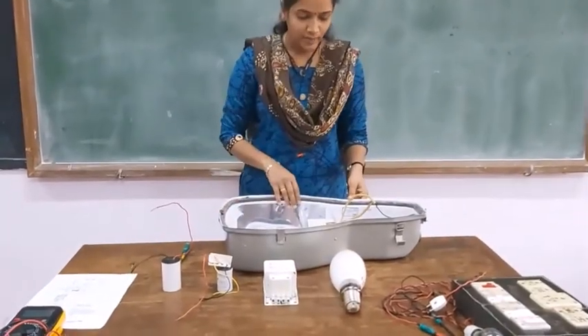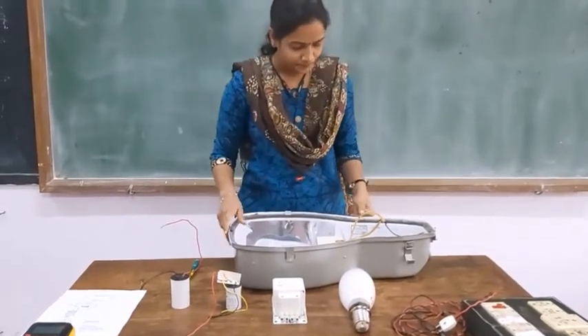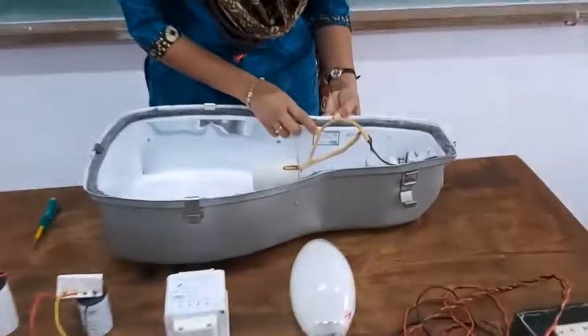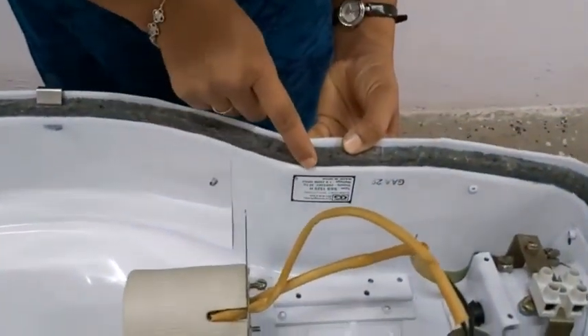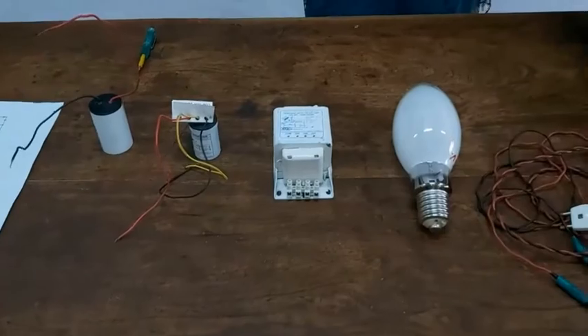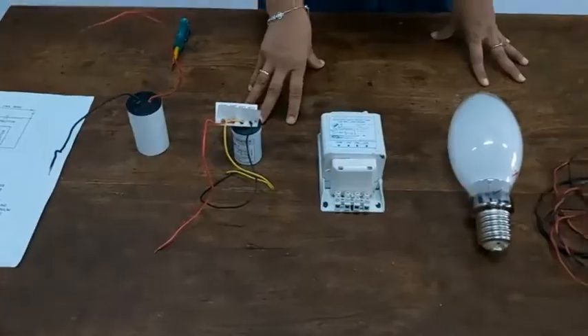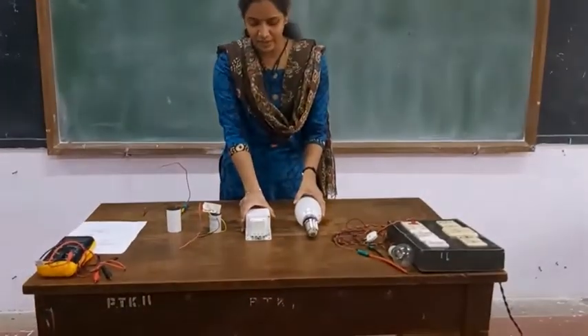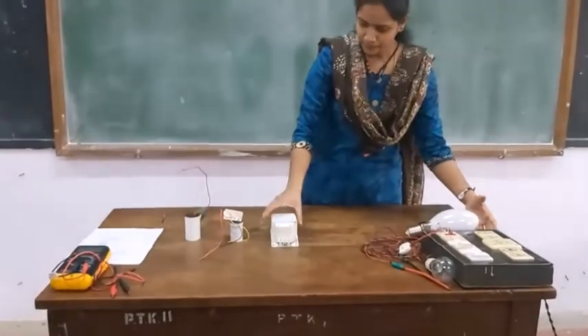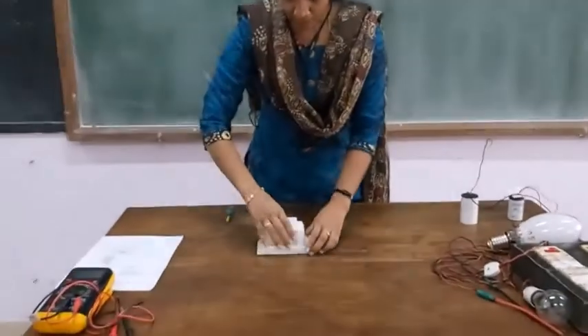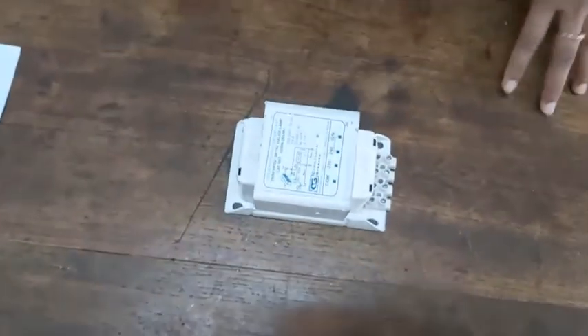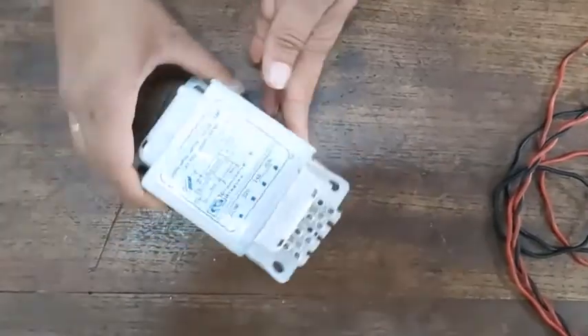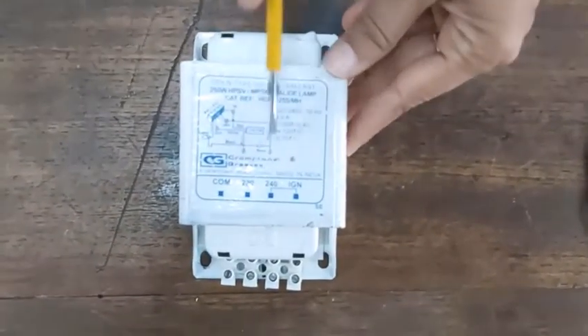Now I have dismantled all the parts of the high pressure sodium vapor lamp set. The specification of this fixture is given here. Now I am going to do testing of each part of the lamp set. I am going to do testing of the ballast or choke using a series test lamp. The specifications of this ballast are provided here.